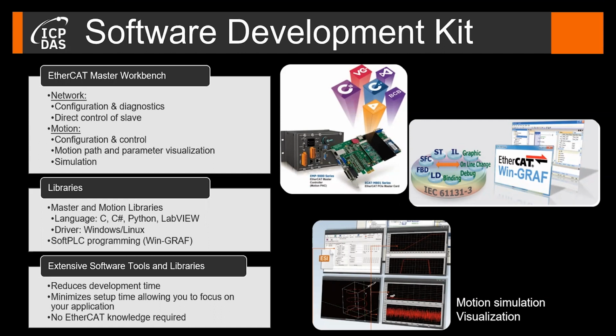In addition, this tool can take direct control of each slave and read its input and set its output data. It supports single and multi-axis motion testing. Basic motion functions such as point-to-point motion and interpolation can be directly commanded using this utility. In addition, this utility contains graphs for tracking the path of the motors and for plotting the motor velocity and acceleration values over time. Further libraries for accessing the EtherCAT network and motion controls are provided.